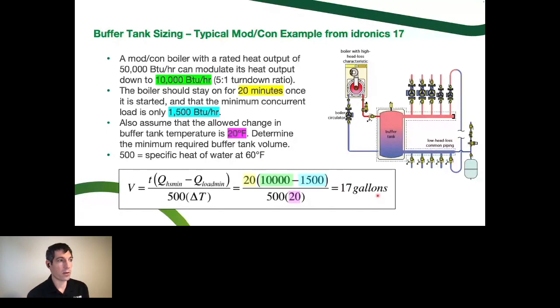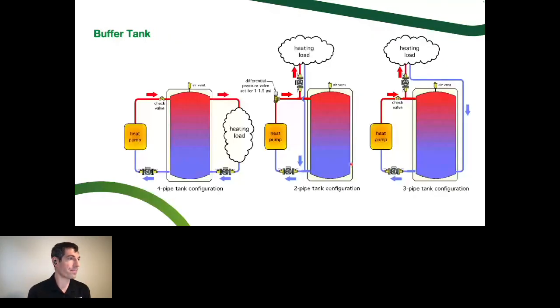With a modulating boiler, it's going to be smaller than you would think. If this were a single-speed boiler or high-low boiler of an older technology, then you would need more buffer capacity because you can't slow down the boiler as much. So this is just to show that you could have a 17-gallon buffer tank that would almost look like a big hydro separator, and that would work in this case.